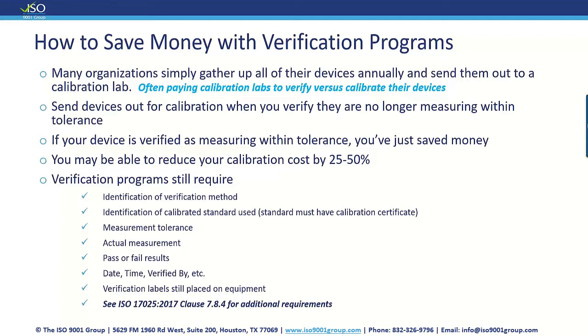So go and run your numbers and see how much money you spent on calibration last year or the year before, or even this year. And think about all of the devices that you just gather up and send out on a routine basis, just like clockwork, and you haven't internally tried to verify those things, but just send them out for calibration. Well, we clearly see in the 3 standards I gave you that calibration or verification is totally acceptable. So your verification program still has to be stringent, right?